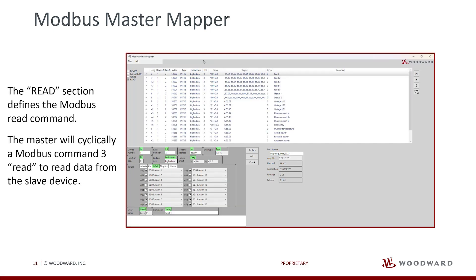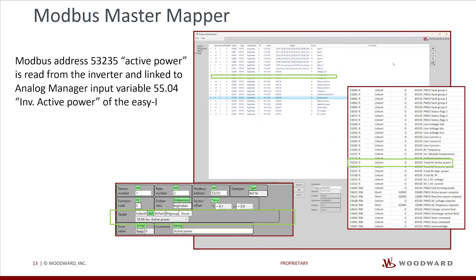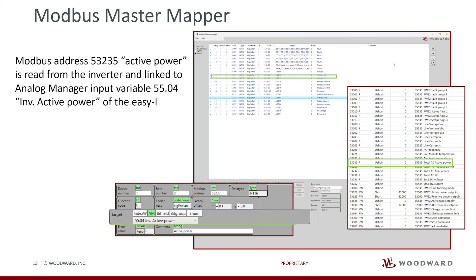The read section defines the Modbus read command. The master will cyclically send Modbus command 3 — read — to read data from the slave device. The list is always automatically sorted by: 1) device, 2) rate, and 3) Modbus address. We want to read out the total AC active power value. To have the active power value from the inverter available in the easy-I, we need to link Modbus address 53,235 to analog manager 55.04 INV active power of the easy-I.